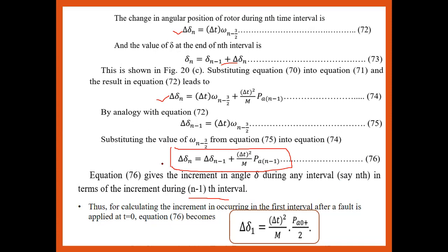This gives the changes in the load angle from the swing equation. The effect on Pe and the accelerating power is important. For the first interval after the fault is applied, equation 76 becomes: Δδ_1 = (Δt²/M)·Pa_0·(1/2). This is the rate of change of load angle or power angle in the first interval after the fault.